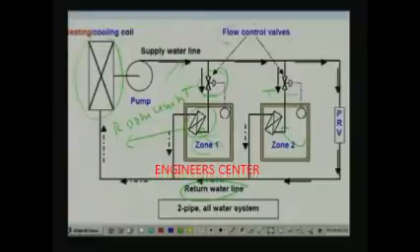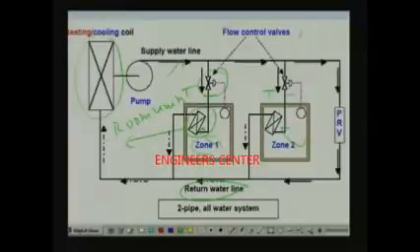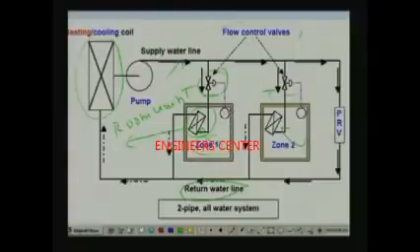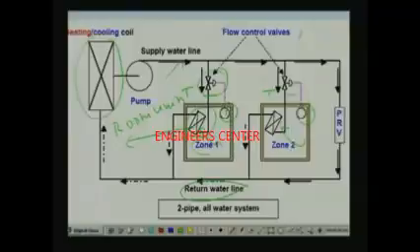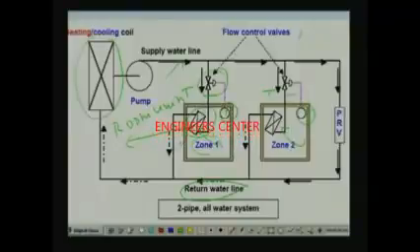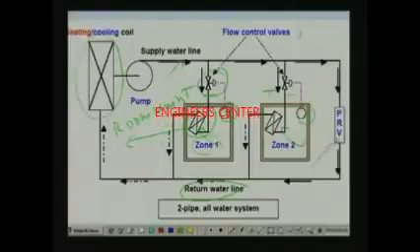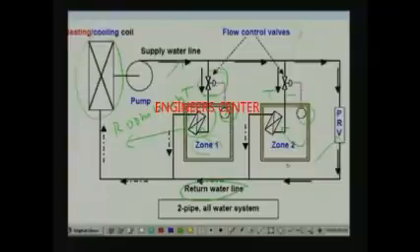The capacity of each zone is controlled by controlling the flow rate of the hot or cold water using flow control valves. You can control the flow rate to the conditioned space and thereby control the required capacity. The flow control valves are controlled by the zone thermostats — if the load is less, the flow control valve is closed and less water is supplied to the room unit. A pressure relief valve (PRV) is also required for balancing the flow rate.